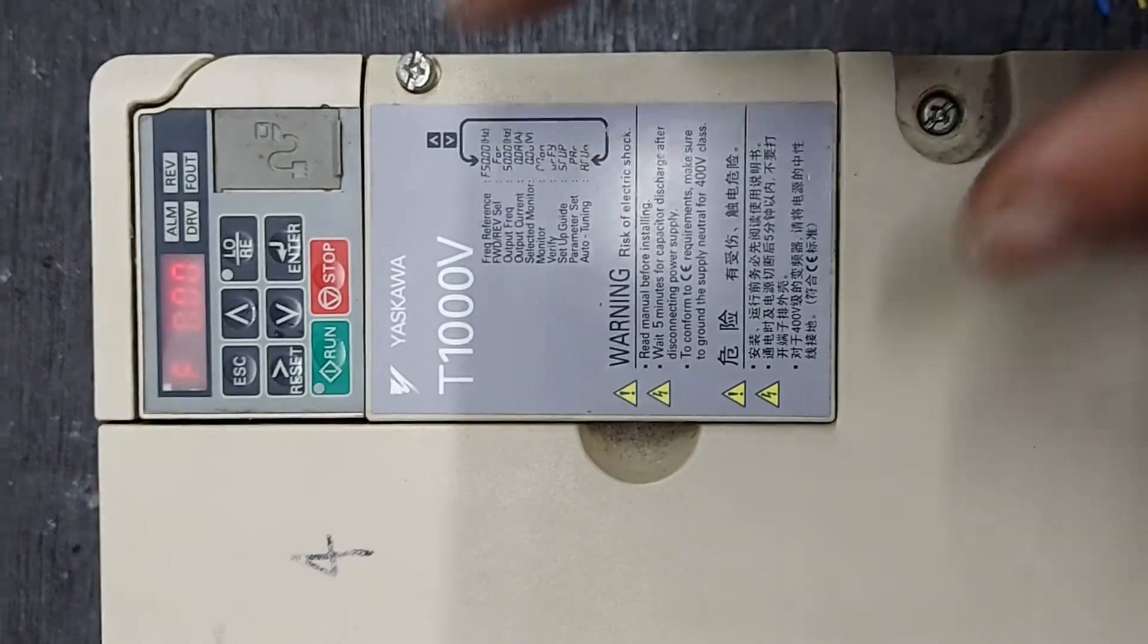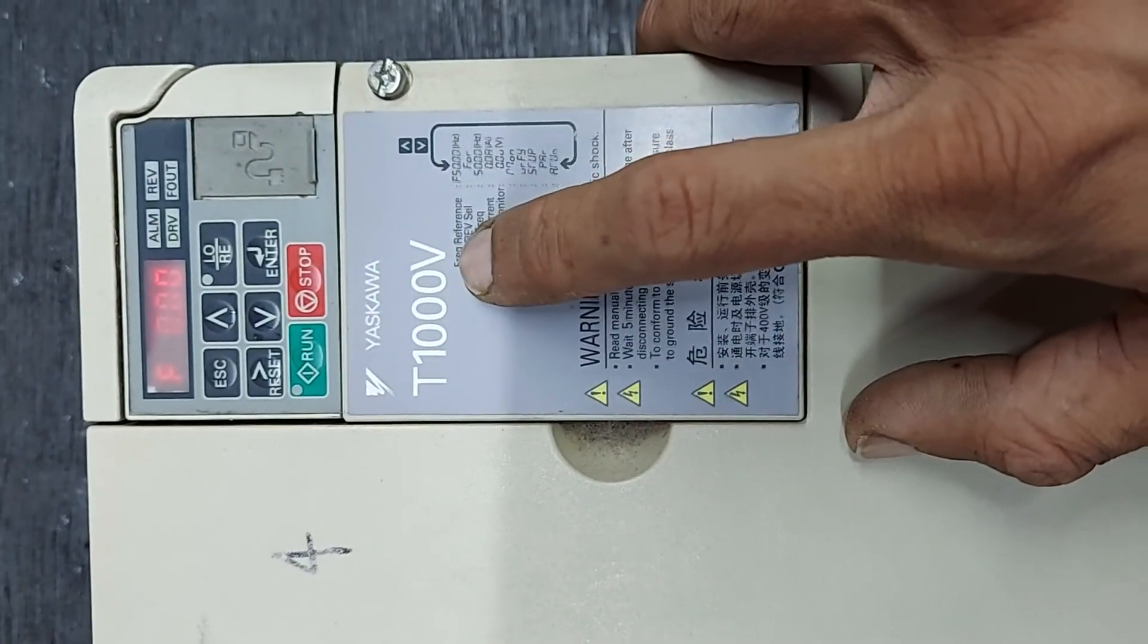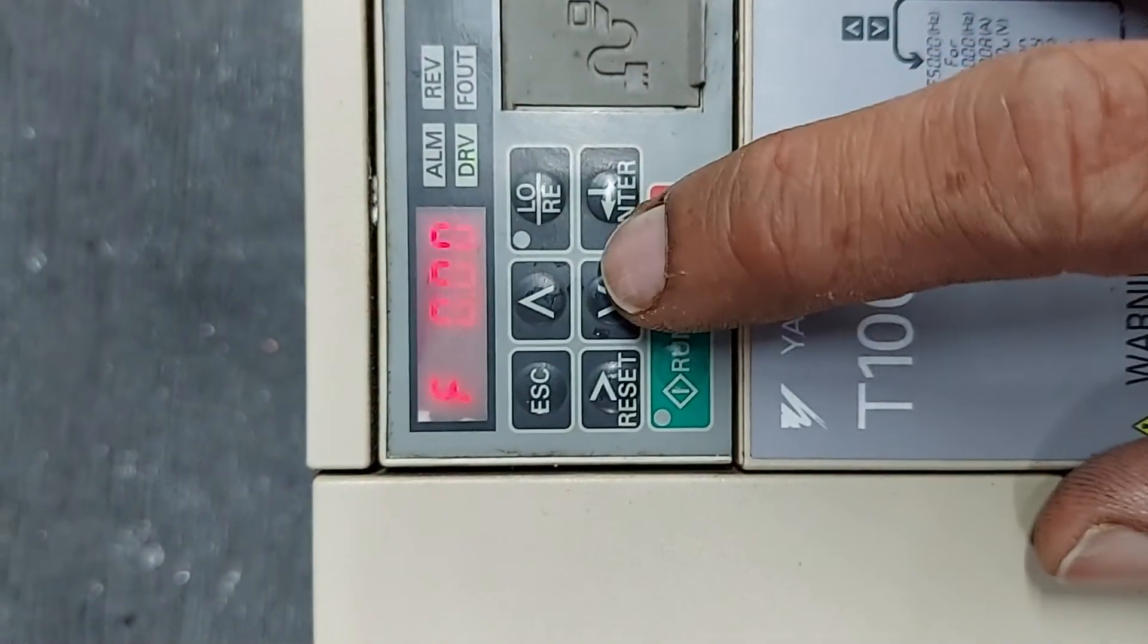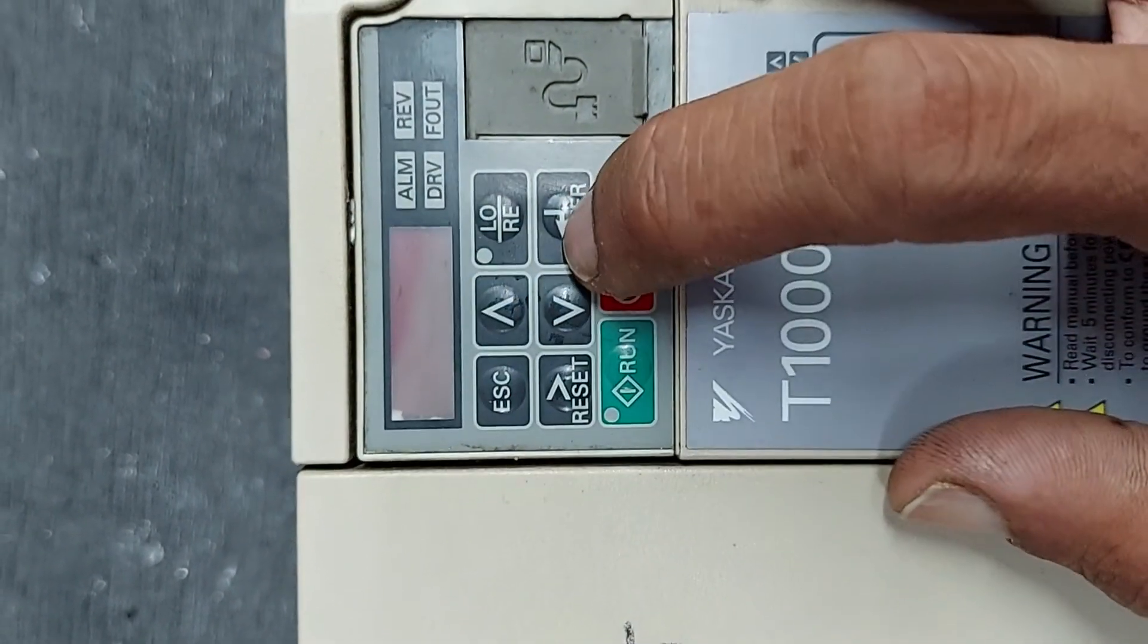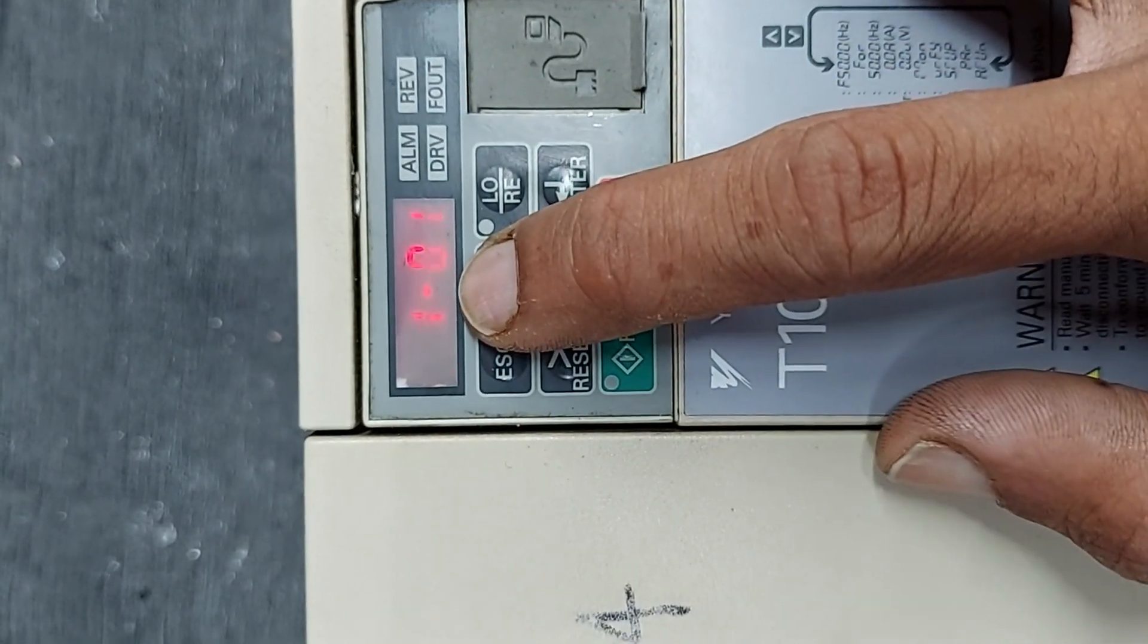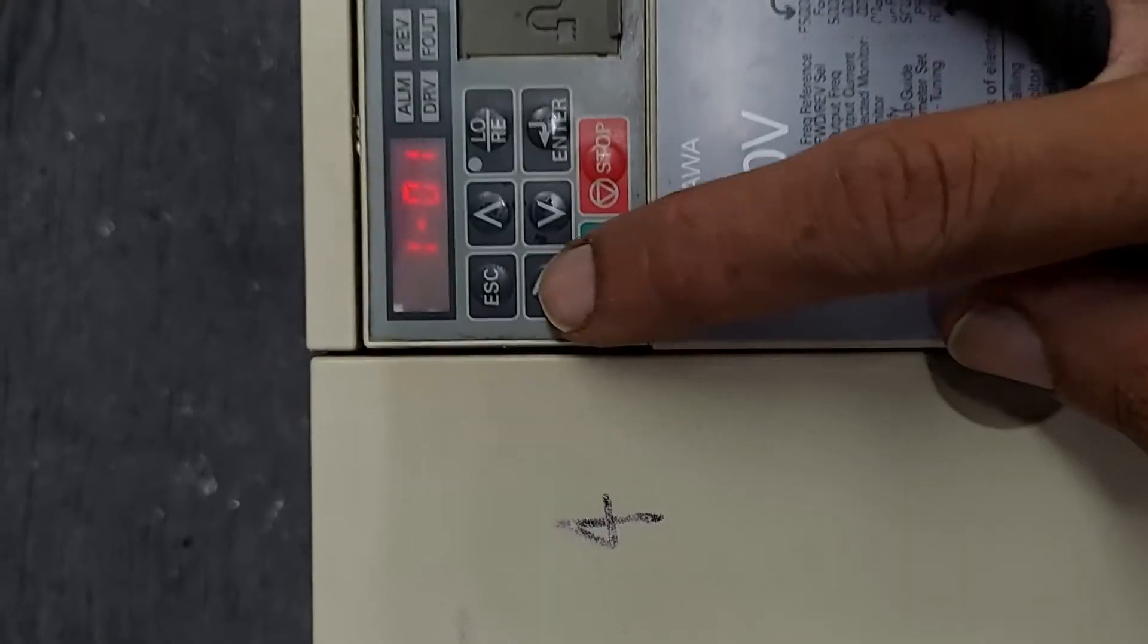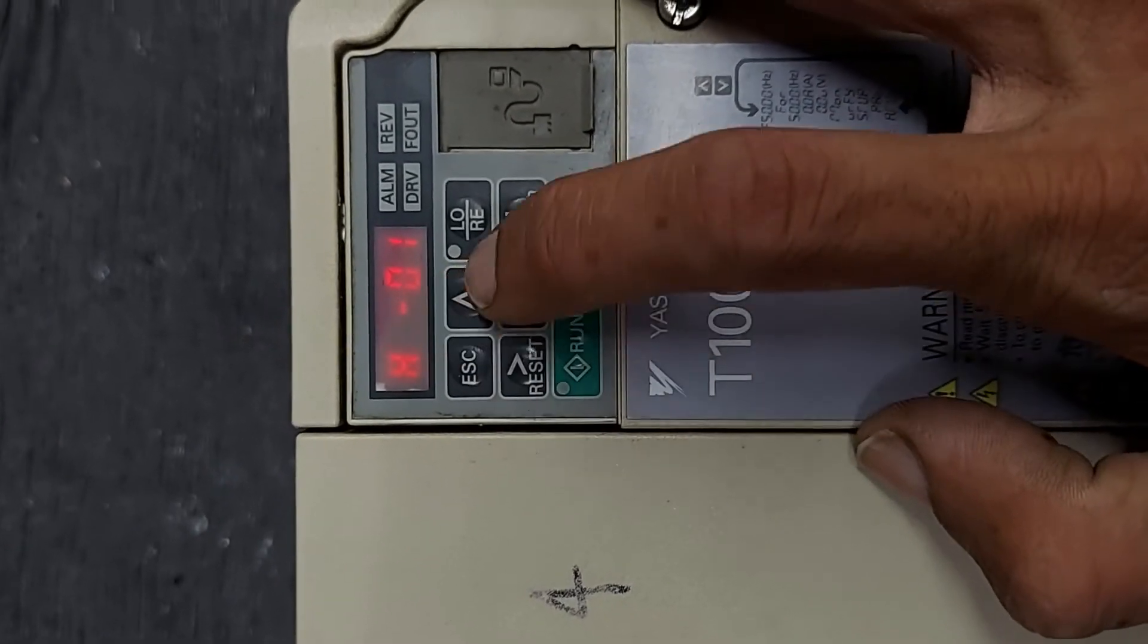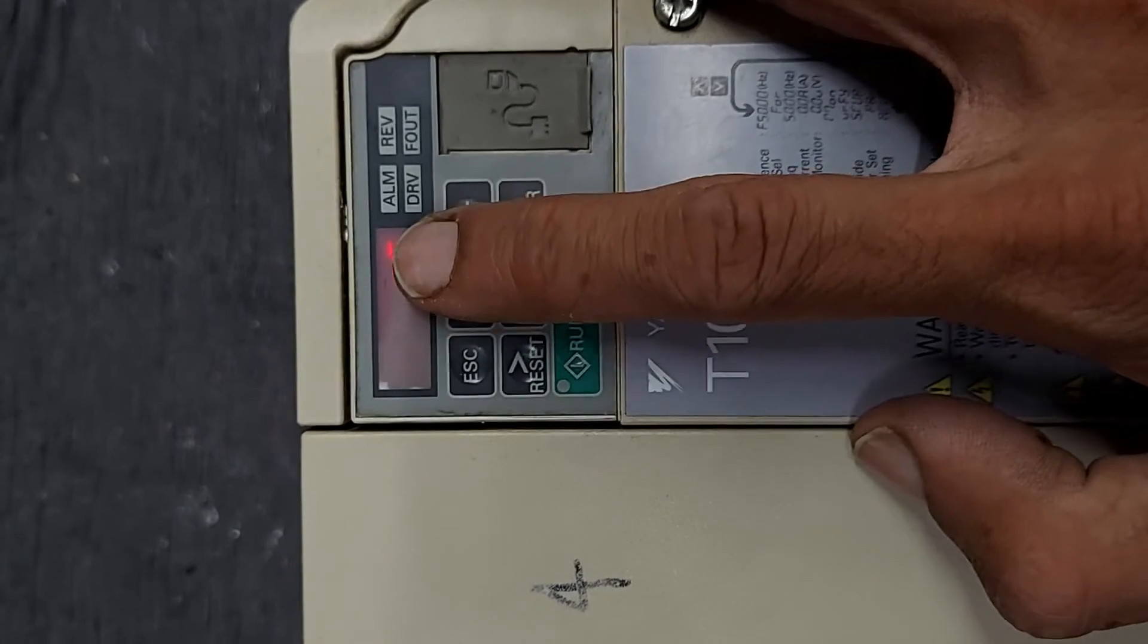Now I am using the Yaskawa T1000V VFD, so let's jump into the parameter. Down, down, we have to set the h5, h501. This is the slave ID. The default value is 1.